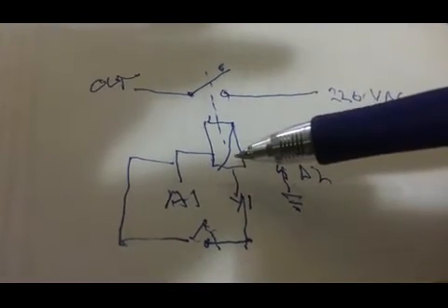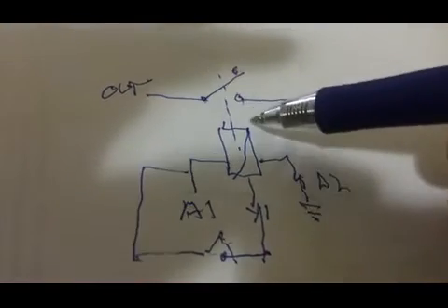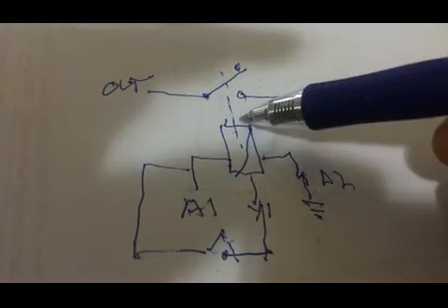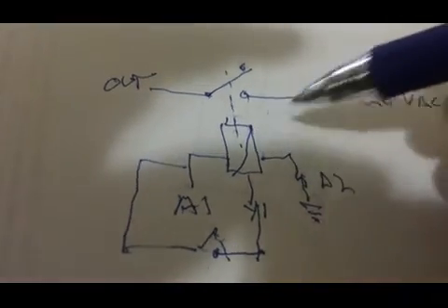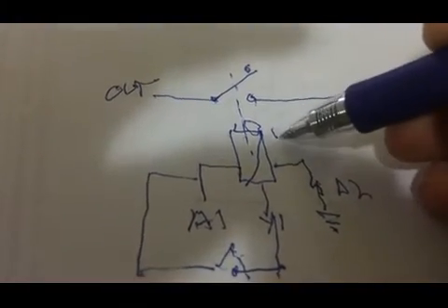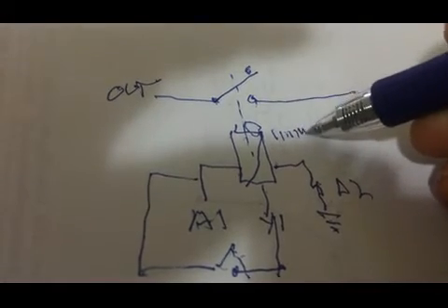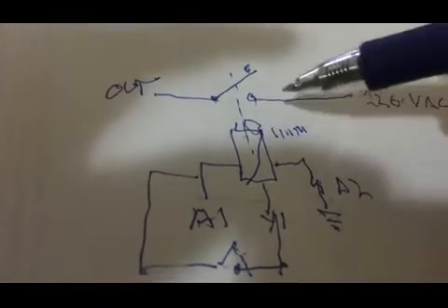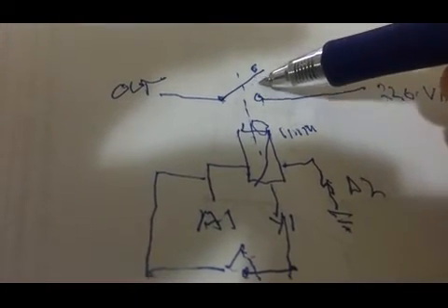When it's going to pull, because this is on-delay, there is a timer on top of it. In the timer, if we select like one minute, then after one minute it will connect here. So there will be a one minute delay.